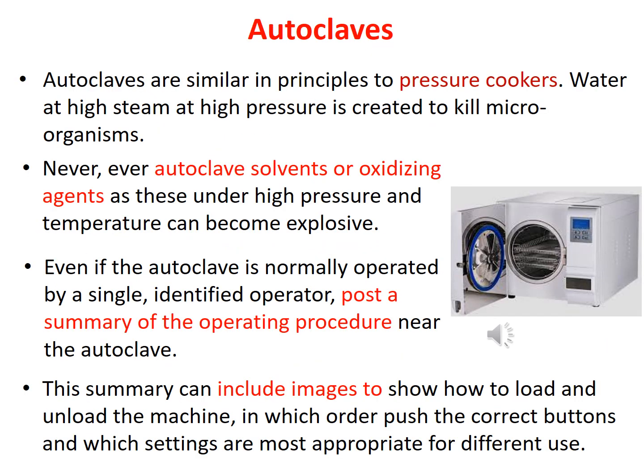Let's talk about autoclaves. These are also commonly used equipment in the lab to autoclave all kinds of contaminations. To avoid any contamination, you prepare some solutions, etc., and then autoclave them. They work like pressure cookers, with high temperature and high steam inside the equipment, and automatically they produce well-autoclaved products. But make sure not to autoclave some solvents or oxidizing agents, because autoclaves work at high temperature and high pressure. These solvents and oxidizing chemical agents can become explosive if you autoclave them. Always check, when you are going to autoclave any chemical, whether the instructions show that you can autoclave it or not.